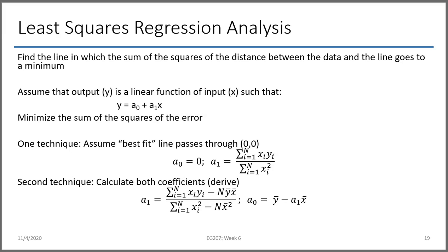Now, let's talk about least squares regression analysis. This is a process that allows us to fit a line to our calibration data. Now, why are we talking about a line? Well, first, it's the most simple way to have a calibration. I would say that in general, in calibrating instruments, you don't want to have anything that's not a line unless it's very clear that you don't have a linear relationship. So I would always assume that the input-output relationship is linear unless otherwise specified.